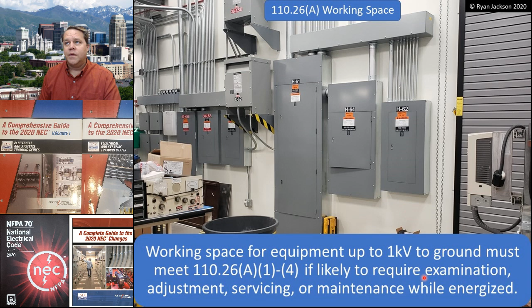So A1 talks about the depth of the working space, and that's of course 3 feet or 3.5 or 4 feet, depending on voltage and conditions. And bear in mind, we're only going up to 1,000 volts today. A2 talks about the width of the working space, and that's the full width of the equipment, but never less than 30 inches. And then A3 talks about the height of the working space, and it says the working space extends from the grade, floor, or platform up to 6.5 feet, but never less than the actual height of the equipment.